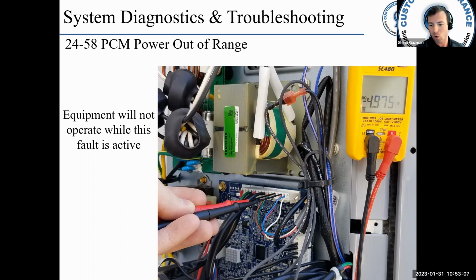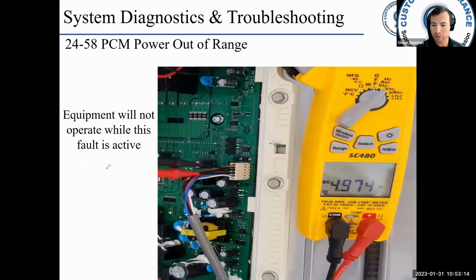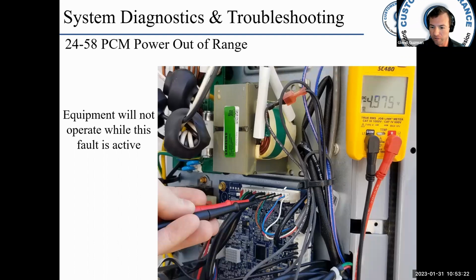If I read a low voltage here and it was connected to the VFD, then my next step would be to pull this plug off the VFD and then check it again. Check it here and see, do I have the 5 volts?